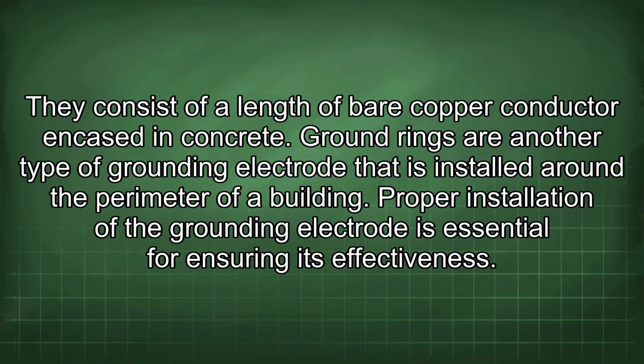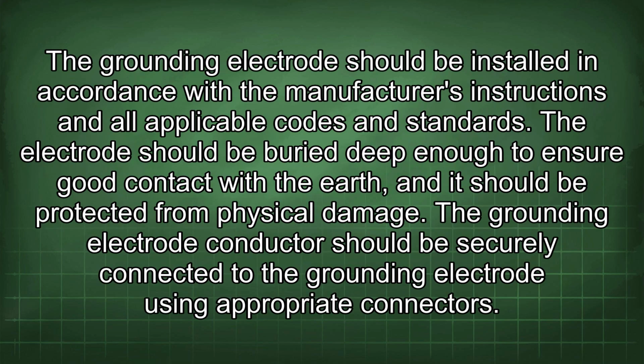Proper installation of the grounding electrode is essential for ensuring its effectiveness. The grounding electrode should be installed in accordance with the manufacturer's instructions and all applicable codes and standards. The electrode should be buried deep enough to ensure good contact with the earth, and it should be protected from physical damage. The grounding electrode conductor should be securely connected to the grounding electrode using appropriate connectors.